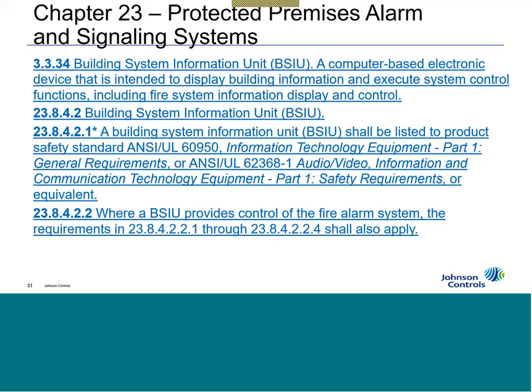So for protected premises, Chapter 23 got involved, and they said, okay, let's start to use this thing. Let's define the hardware first. So a building system information unit, BSIU, shall be listed to product safety standards, not UL 864 for fire, but UL 60950 for IT equipment, or 62368 for audio, video, information, and communications equipment. The computer that we're talking about is something that's, I'm going to say, almost off the shelf.